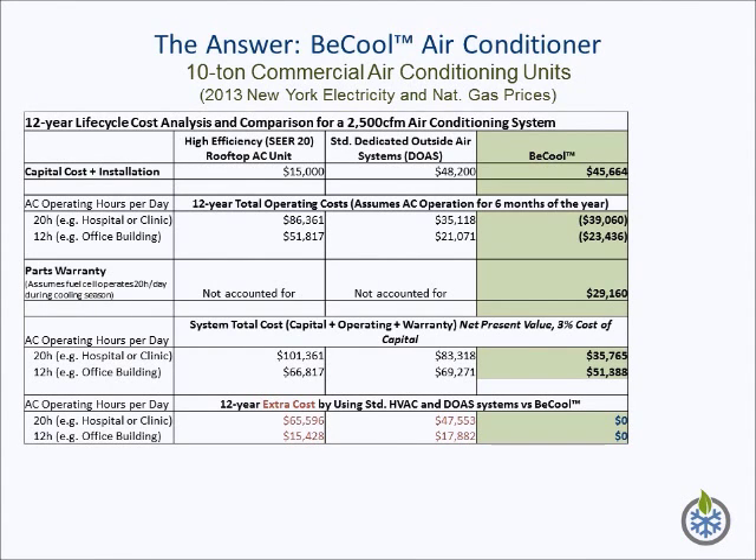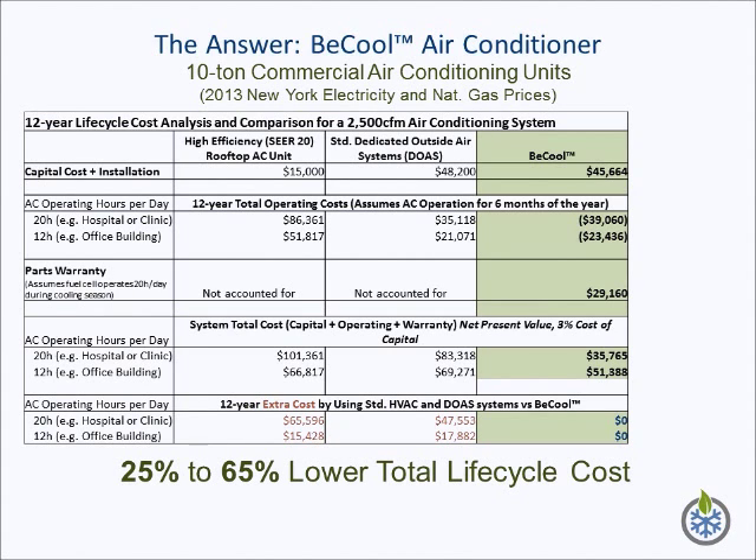The competitive advantage of the BeCool product is significant. To illustrate this, a comparison of costs associated with existing high-efficiency rooftop air conditioners, dedicated outside air systems, or DOAS, and projected costs for a similar BeCool system are shown in the table. This analysis assumes all these units have similar specifications. They provide 2,500 CFM of air to the building and 10 tons of cooling. The BeCool system also produces 15 kW of electricity and consumes natural gas at a rate of 43 kW thermal, based on its lower heating value. The result shows significant life cycle cost savings ranging from 25% to 65%, depending on how the system is used.